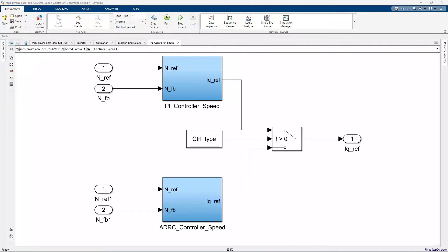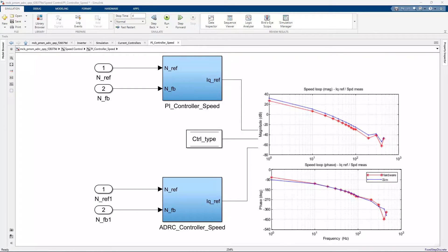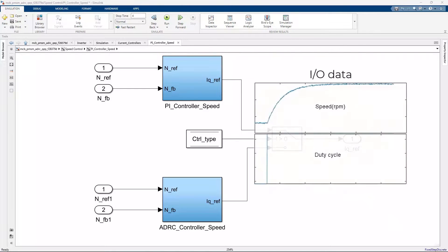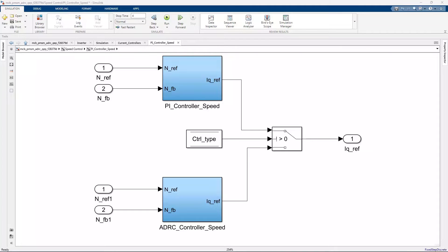One would need to estimate the plant model for each of the loops using either frequency response estimation or input-output test data and then use the model to tune the PI gains. There is extra effort involved if one wants to consider other operating points and account for external disturbances.